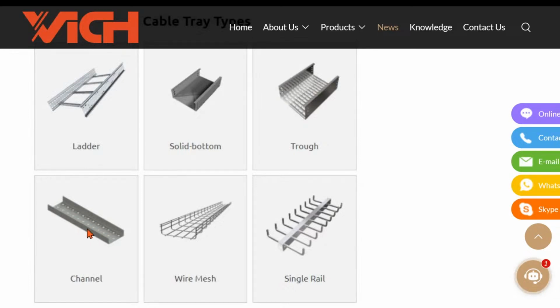It is much smaller, okay? And it is usually limited in width. And these typically will hold things like Cat5s, communication, signaling, not so much power because they're limited in width. And also you're going to see, sizing wise, they're typically limited as well. And then of course you have the wire mesh type. And then you have what's called the single rail type.